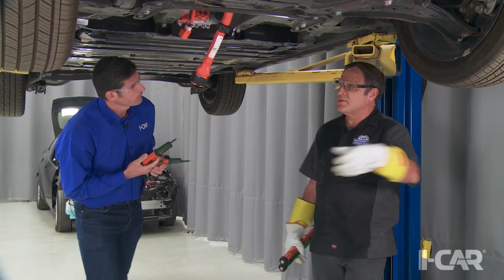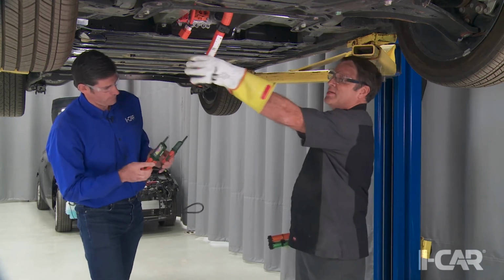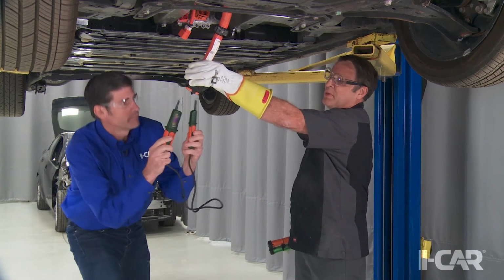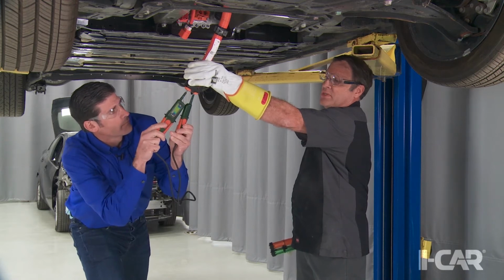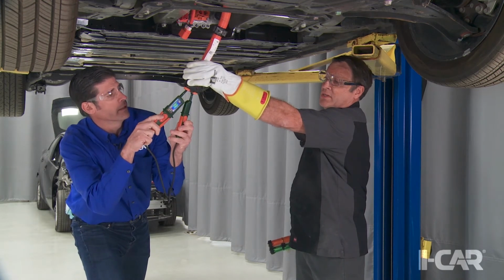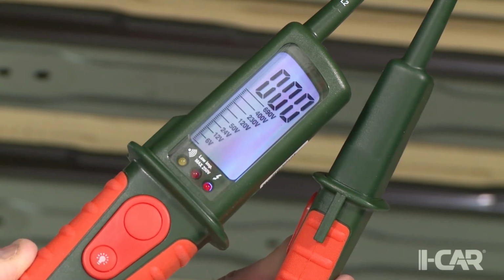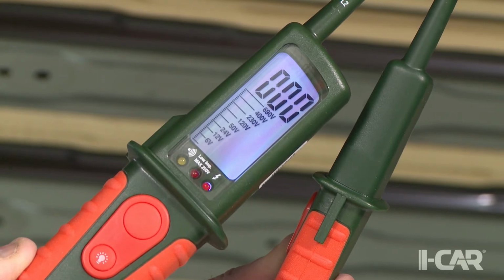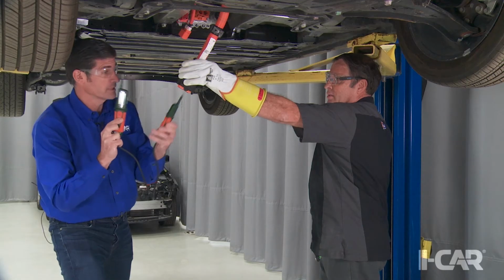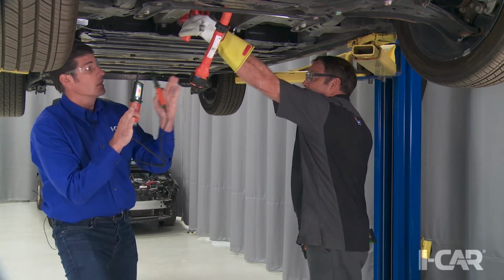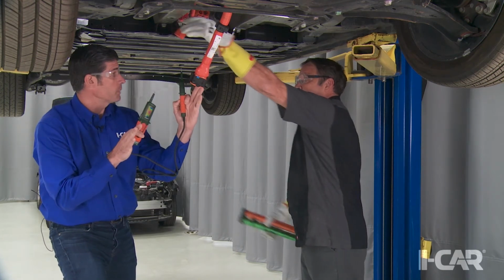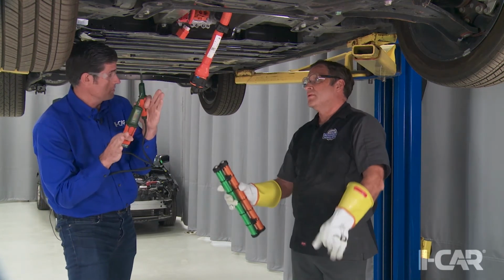Interesting that the procedure says you're supposed to measure for 5 volts or less at this connector, and I'd expect to see 0 volts as you test up here. I'm not sure what the meter is reading since I can't see it, but I'll hold it toward the camera so our colleagues can see it. 0 volts, we verify 0 volts. Now I verify high voltage plus to high voltage minus.